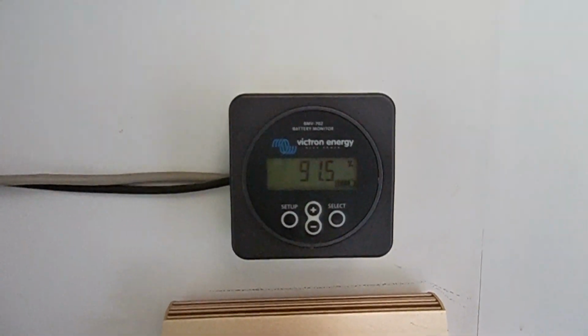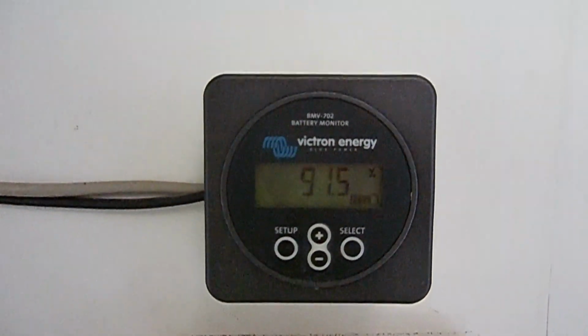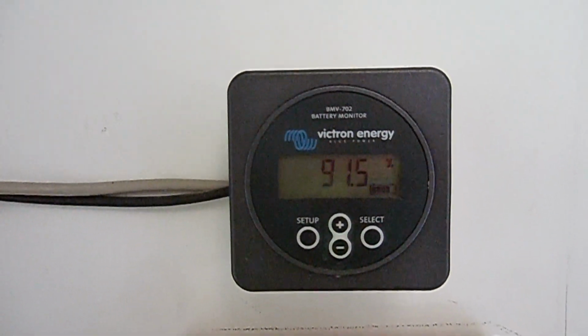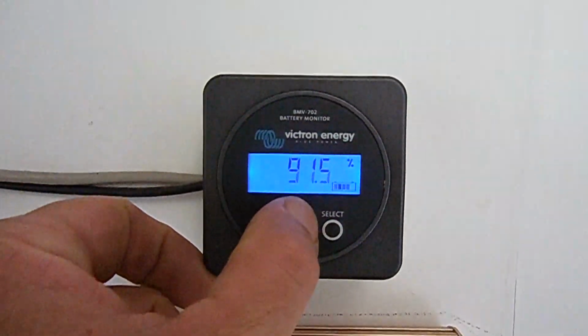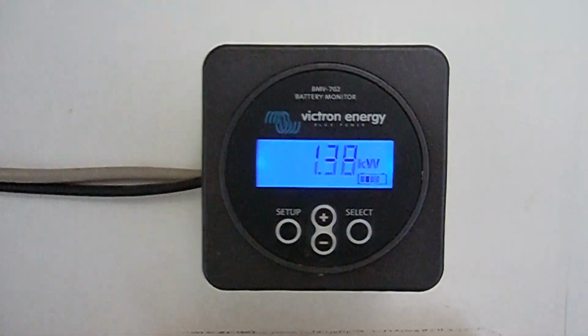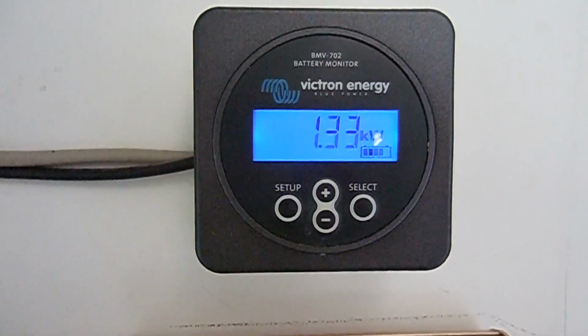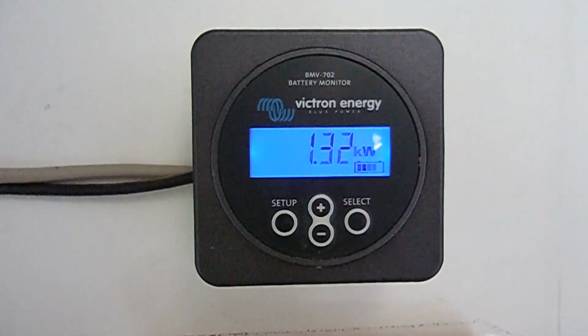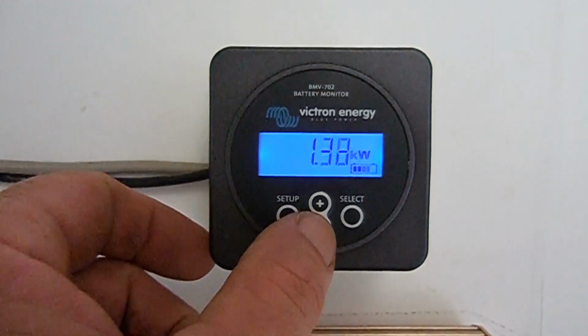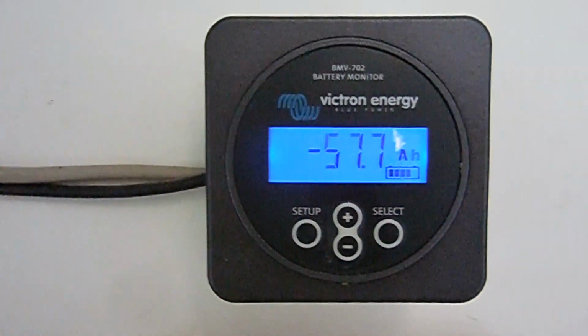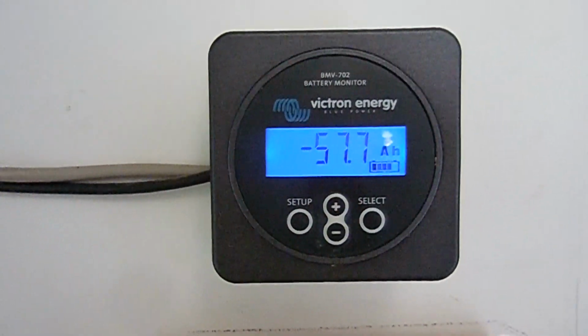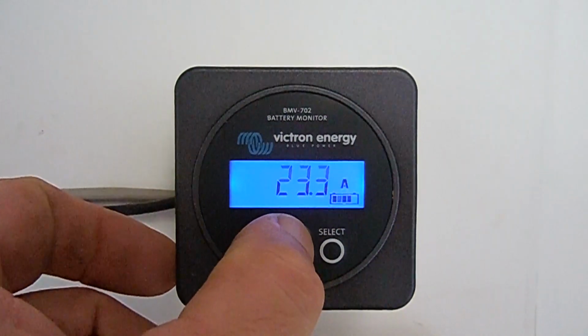That bus bar is connected up here to this Victron energy meter. You can see our battery percentage is 91.5%. We're probably taking a bit of power out now. So we've got 1.3 kilowatts coming in. You can see we're down 57.7 amp hours out of the battery bank.